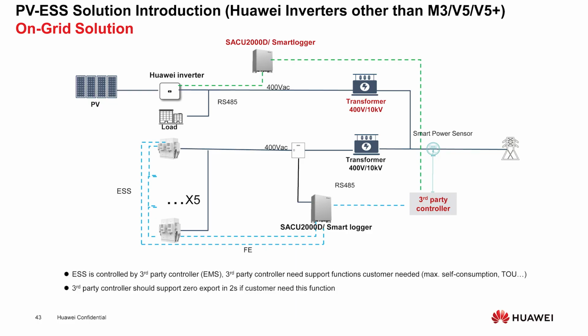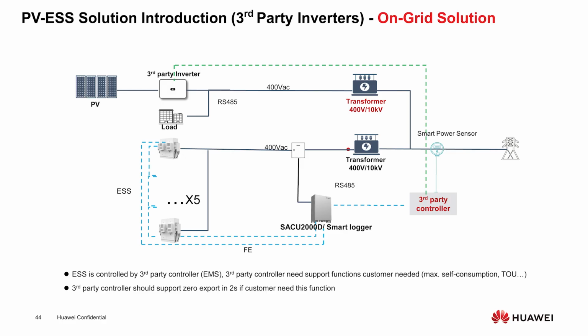Your PV solution, an on-grid solution without Huawei inverters. If there's an on-grid solution without Huawei inverters, we have third-party inverters. The only difference is that between the inverters and the ESS, you need to have an isolation transformer, so there's no backfeed DC into your inverters. All the new Huawei inverters don't need this isolation transformer because we have the communication between them, okay? But if you're using third-party inverters, you need to have an isolation transformer in between that prevents the storage solution from feeding DC back into the inverter, okay?